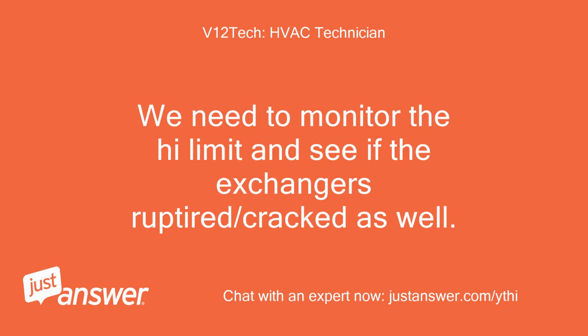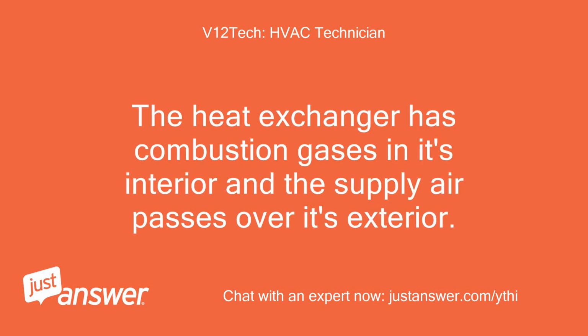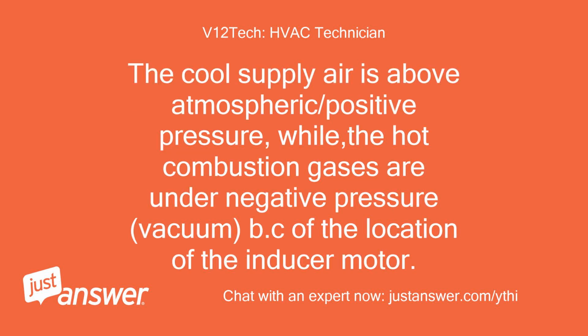We need to monitor the high limit and see if the heat exchanger is ruptured/cracked as well. The heat exchanger has combustion gases in its interior and the supply air passes over its exterior. The cool supply air is above atmospheric/positive pressure, while the hot combustion gases are under negative pressure, vacuum, because of the location of the inducer motor.